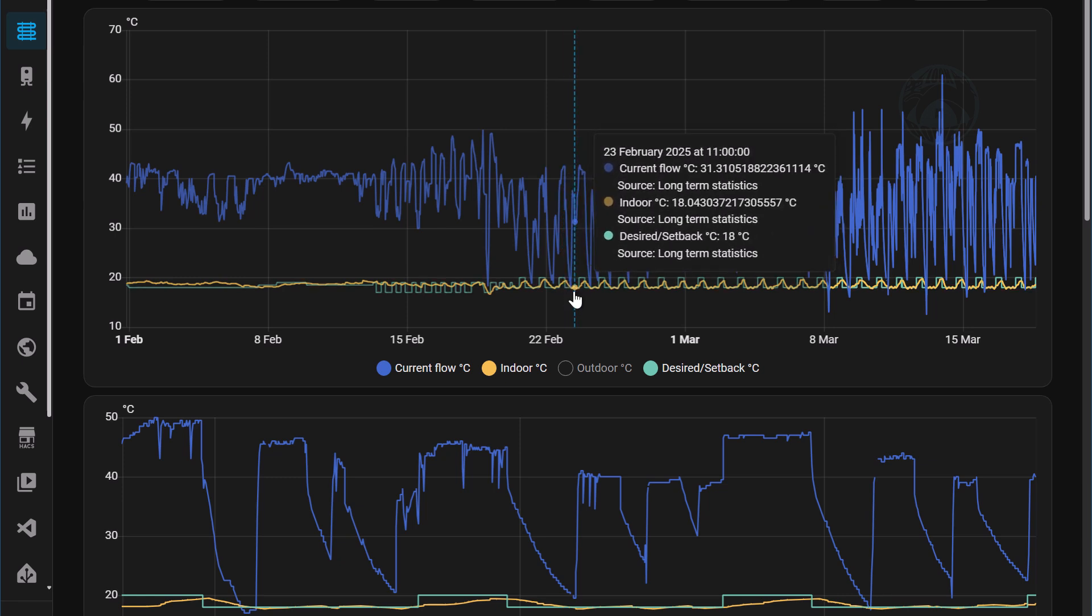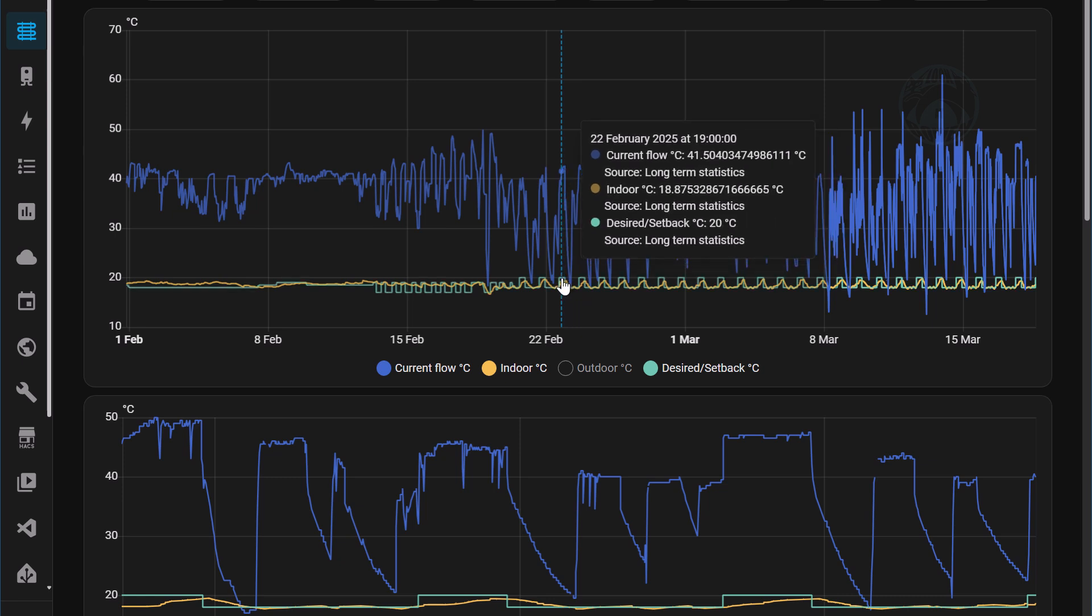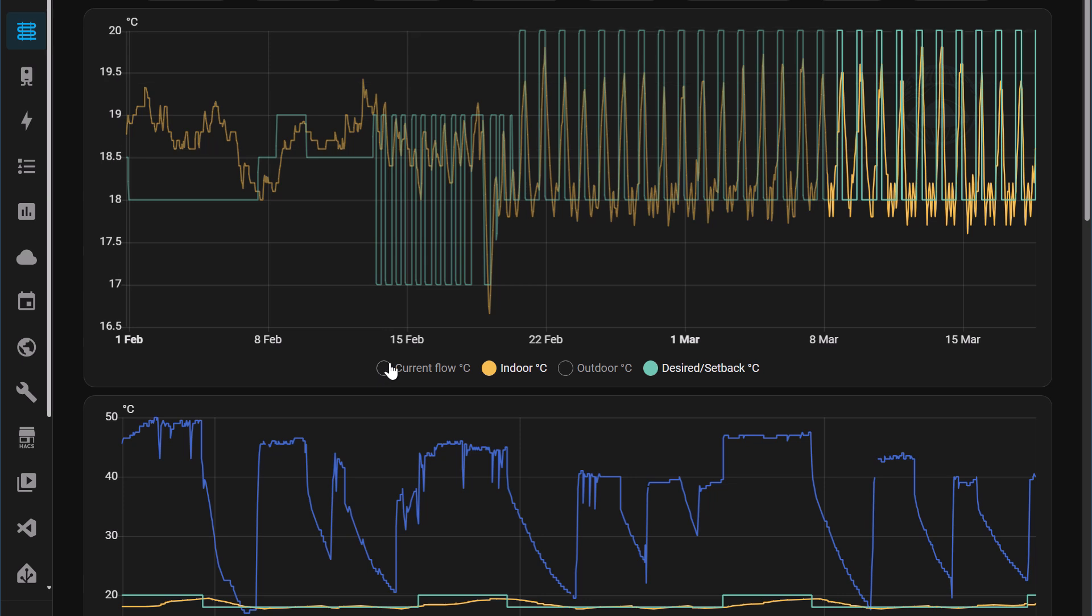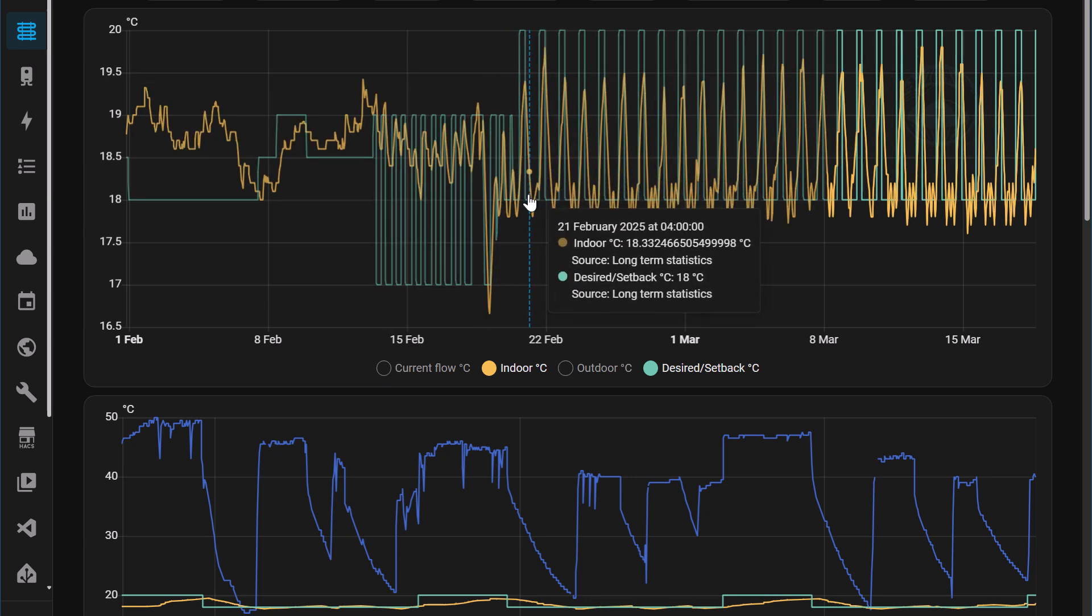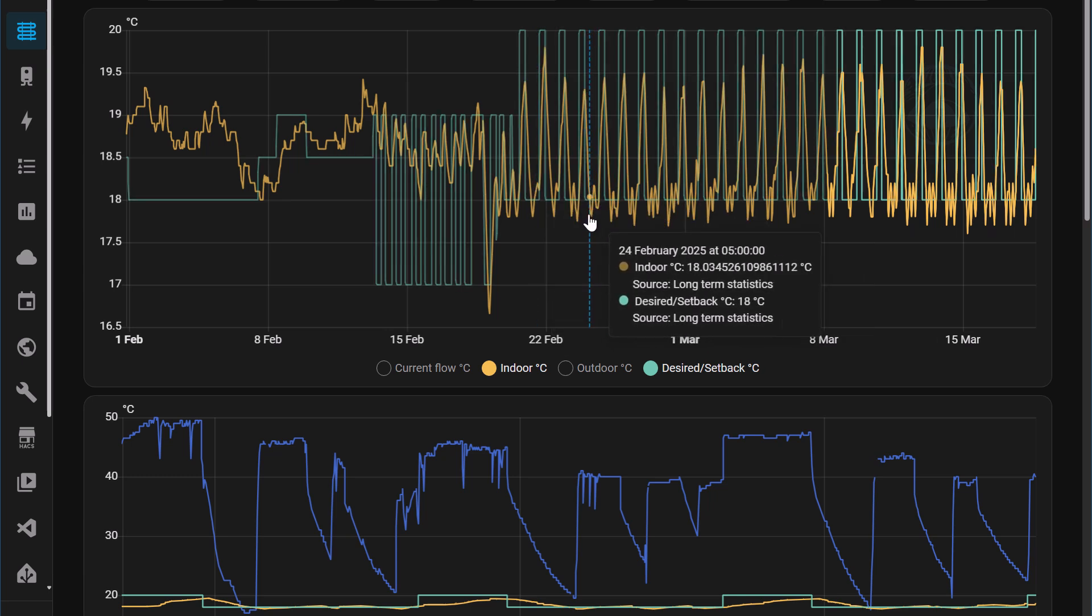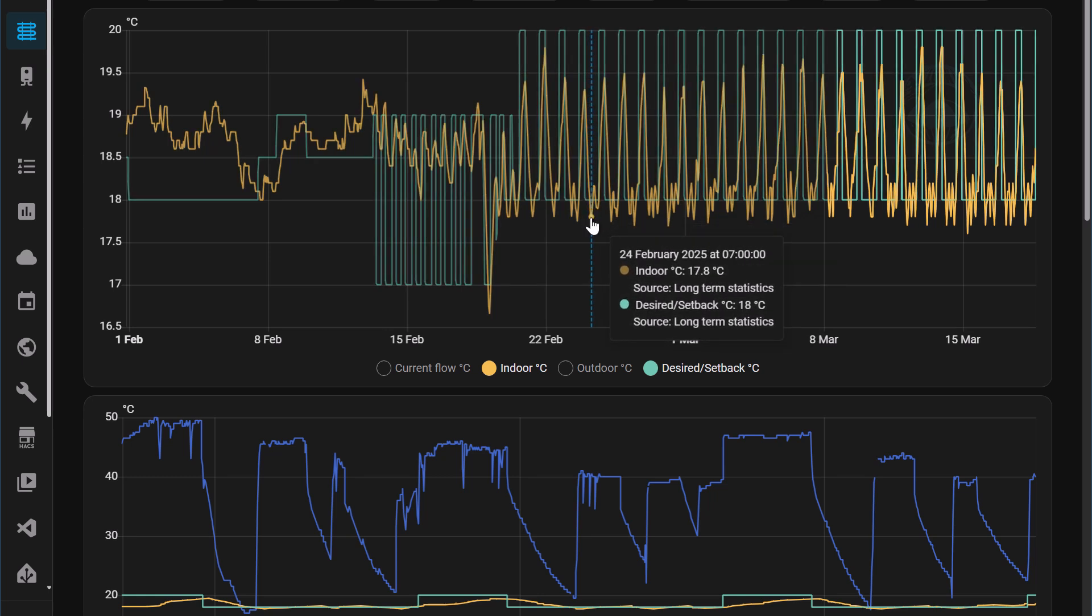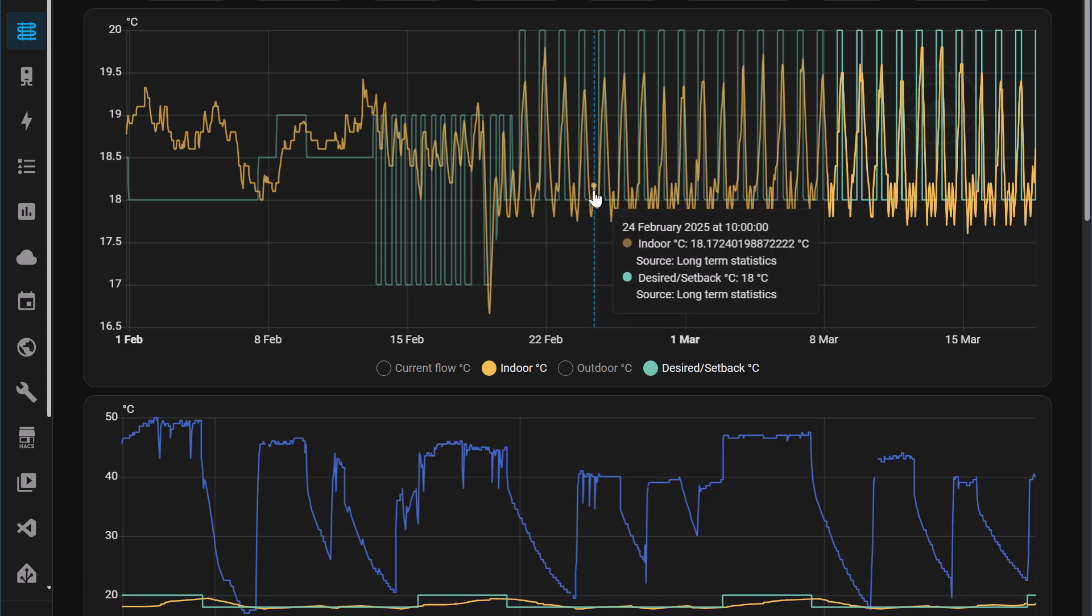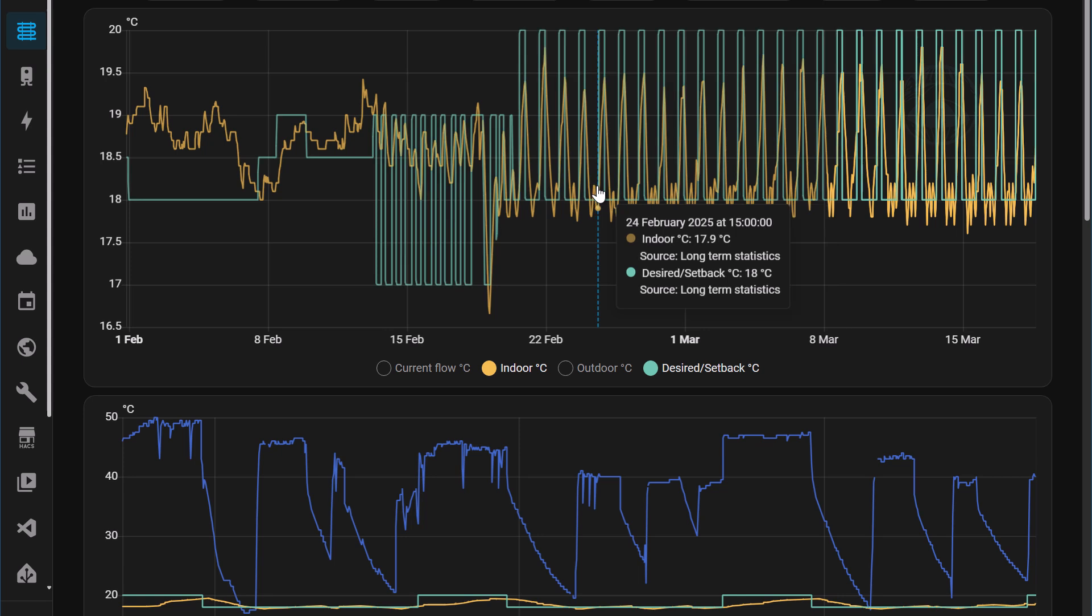If it's a very cold morning, because bear in mind, this timer is only on from 4 in the afternoon till 11 at night. If it's a very cold morning, what tends to happen is you see the indoor temperature drops below the setback temperature and then it fires back up. An example here would be this day over here, the 24th of February. You can see it's dropped below the setback temperature. It's got to about 17.9, so 0.1 degrees. The boilers then come back on. It goes right back up to around about 18.17 or maybe call it 18.2 and then the boiler switches off.